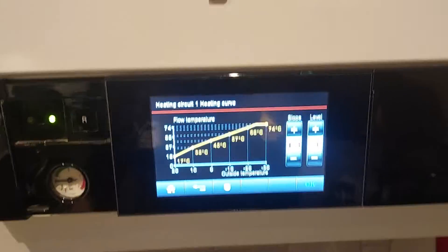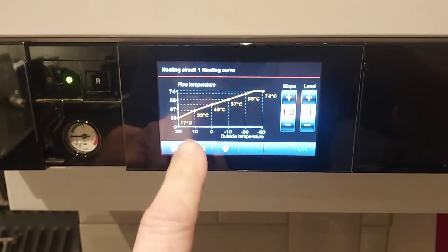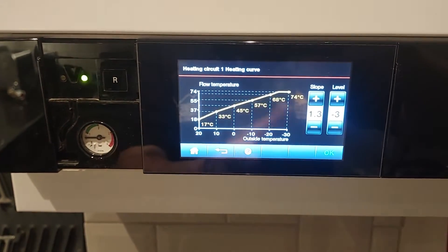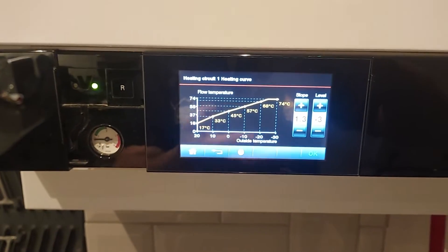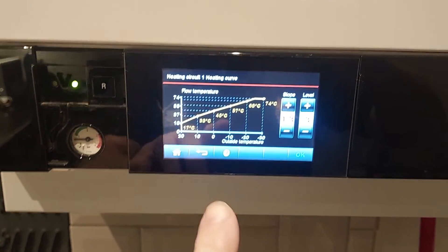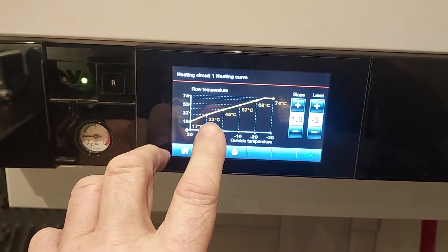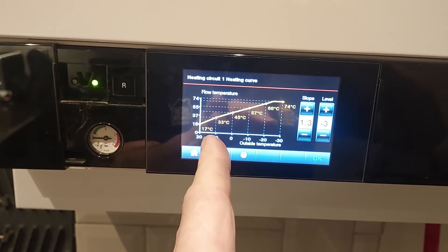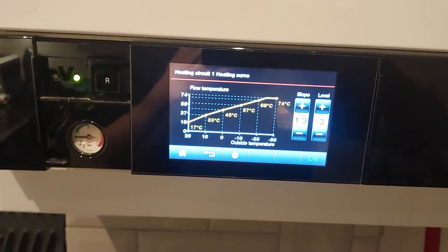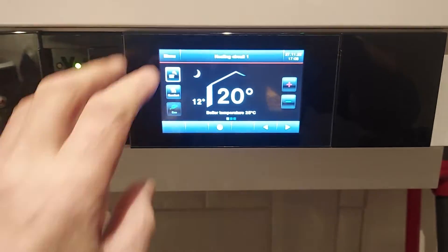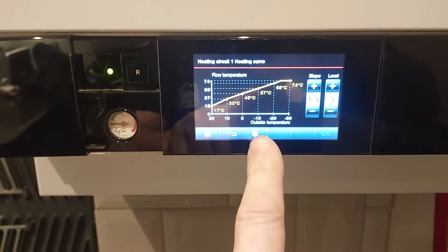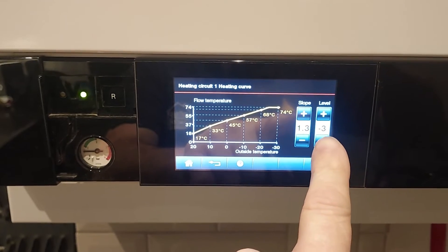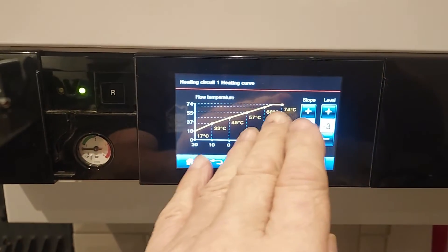The only real heat loss is this doorway and it's not enough. I also don't have a window in this kitchen. So the point is that other factors in the property are actually letting heat into the property. Throughout the house we've got tenants in rooms, TVs, computers and various other heat sources. So actually we don't need the boiler to start heating the property until we get to maybe 17 degrees outside in order to maintain 20 degrees, because there's already enough energy from other sources to maintain that temperature.